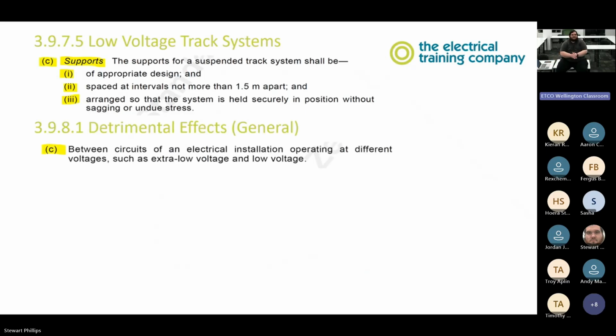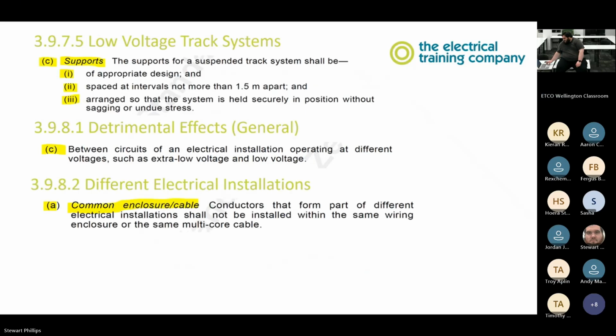Cool. So detrimental effects between circuits of an electrical installation operating at different voltages, such as extra low voltage and low voltage. Common enclosure cables. Conductors that form part of different electrical installations shall not be installed within the same wiring enclosure or the same multi-core cable. So what do you think this rule is talking about?